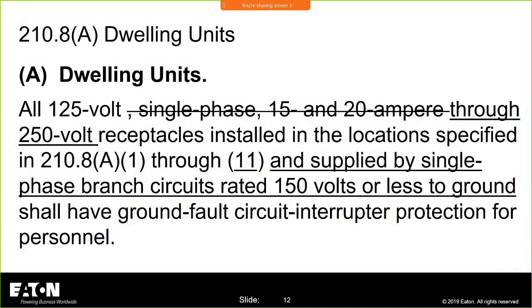Let's take a quick look at dwelling units. We took out the 15 and 20 ampere. So we said any 125 volt or 250 volt receptacles installed in any of those locations, 1 through 11 within the National Electrical Code, have to be GFCI protected. I don't care if it's a 30 amp, a 60 amp, a 50 amp. We didn't put an amp value on it.